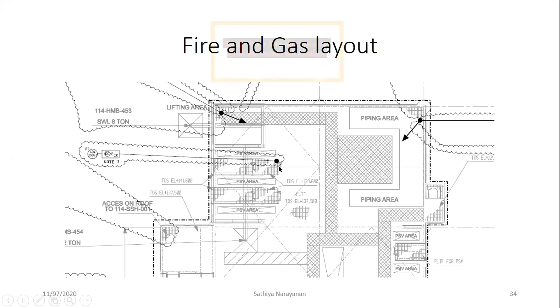Here I have mentioned a fire and gas layout, developed by the process safety department. You have a gas detector placed at this particular area, a gas detector methane, GDM. This particular selection is based on considering which area is actually accessible to the field persons working there. If you place a detector somewhere that cannot be accessed by the employee, then it becomes an issue. So the safety department has to ensure that the gas detector is accessible to the field persons.